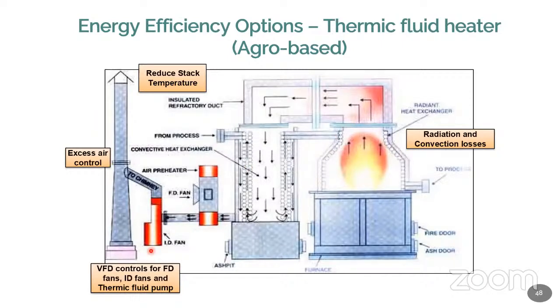Then you can use VFD control for the ID fan and FD fan, based on the temperature, flow, and pressure. You can operate the motor at a lower value or higher value, instead of operating at a constant speed, which takes constant power. If your temperature or pressure is lower, then you can operate the motor at lower speed. I told you in the previous class, when the speed is reduced, power is reduced. Power is directly proportional to the cube of the speed. If the speed is reduced by 10%, 27% of the power is saved in the motor. That is why we are using VFD controlled ID fan and FD fan.